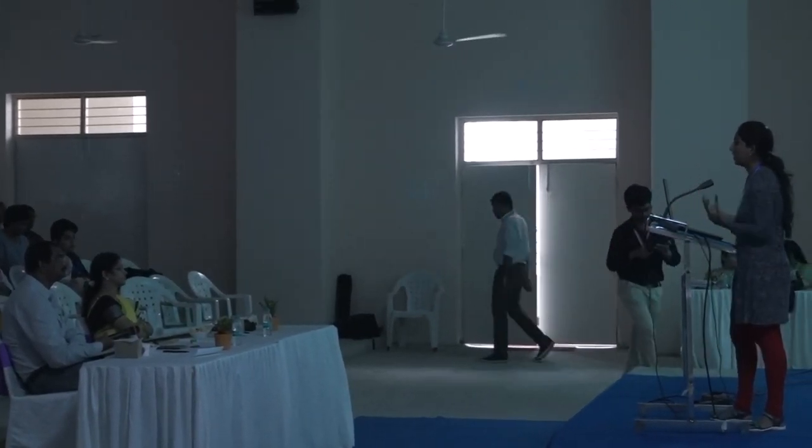A question was asked to go back to the slide showing the photograph of the scanner and explain how it works. The speaker explained that due to lack of time she did not include details on scanner working. Basically, the device — which works with an iPad — emits a trace and collects back reflected data from the object. The scanner then arranges this into an STL file by preparing triangular meshes to build the entire surface. In the scan procedure, bony landmark points are identified and marked.